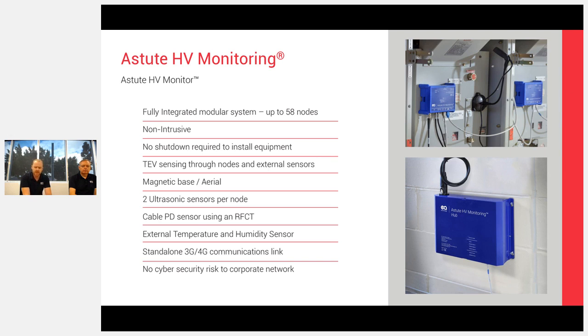What we do with those microphones is we focus them into each of the HV chambers, into your cable boxes, into your buses, to listen to the spouts behind your circuit breakers, so your cable spouts and your bus spouts, all those types of areas, to listen to any crackling or arcing or sparking that's going on.